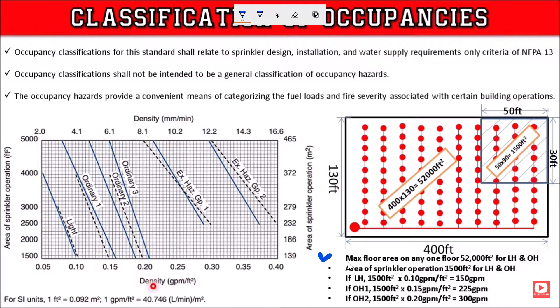Regarding system protection area limitations: the maximum floor area on any one floor — the connected floor area capacity — is set. For light hazard and ordinary hazard, the area of sprinkler operation per NFPA 13 is approximately 1,500 square feet, which is kept as the area of sprinkler operation.